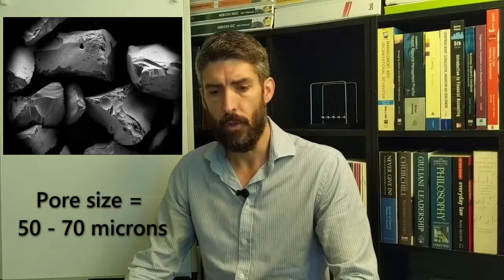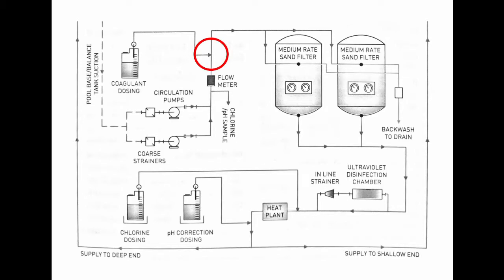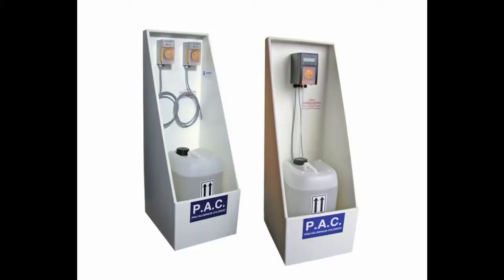Coagulants are substances that get added to the pool circulation system. The best way is to inject them continuously at a very low dose rate directly into the circulation system at some point prior to filtration but after the circulation pumps. One of the most commonly used chemicals is called polyaluminium chloride, or PAC for short.